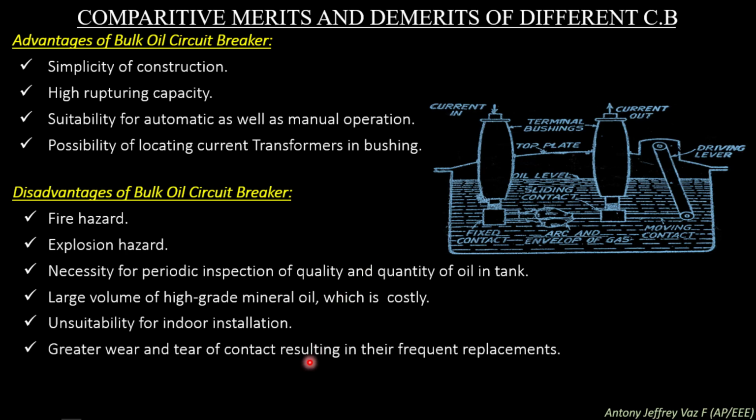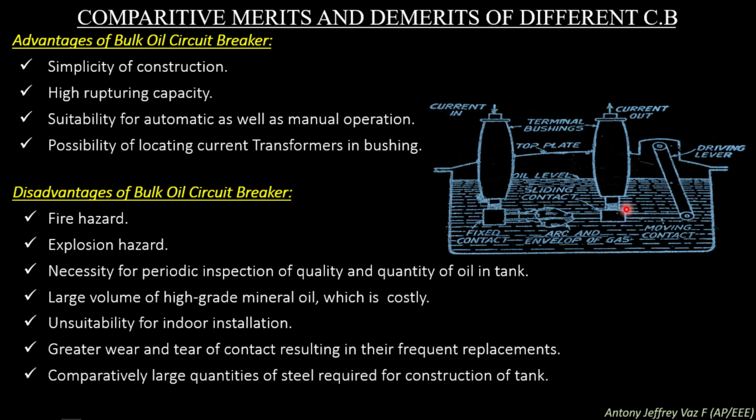Greater wear and tear of contacts resulting in their frequent replacement. Since the contacts move under oil and in the presence of an arc, very high heat is present, so the moving contacts and the levering system have to be replaced very frequently.